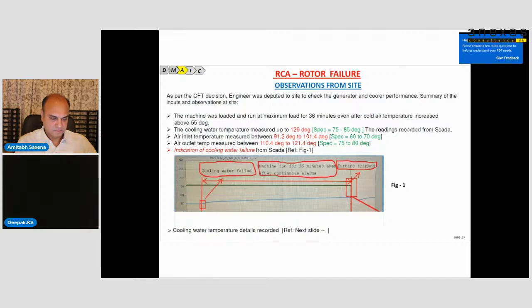Okay. The records were read from the SCADA. Air inlet temperature measured between 91.2 and 101.4. Yes, the spec is 60 to 70. Air outlet temperature measured between 110 and 121 degrees. The spec is 75 to 80 degrees. Yes, we got the indication of the cooler water failure. Cooling water failure from the SCADA reading. You can see that.